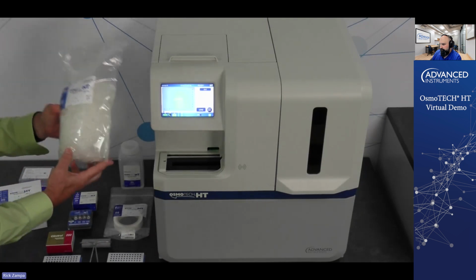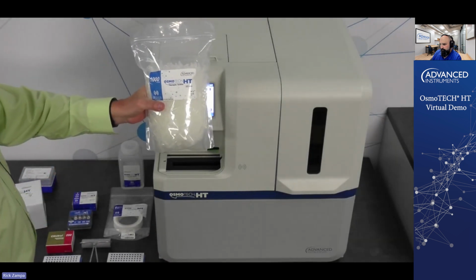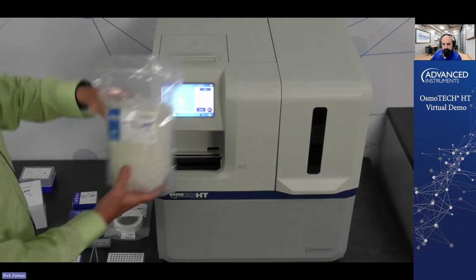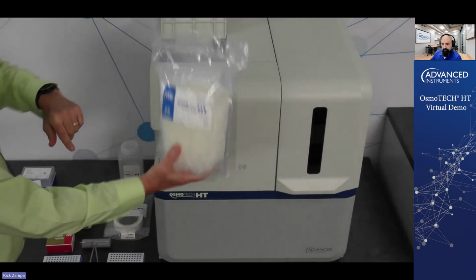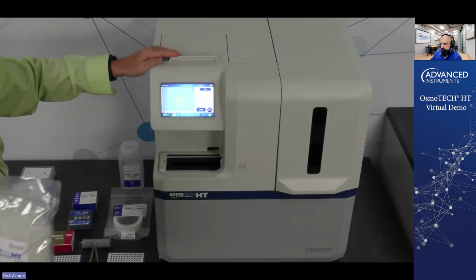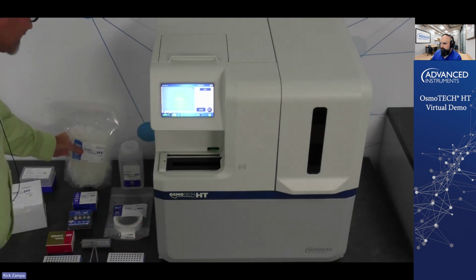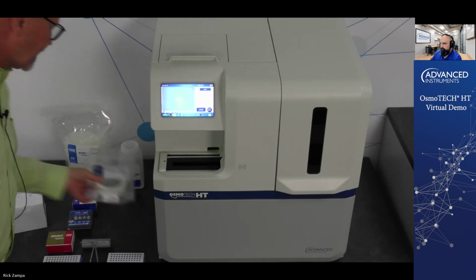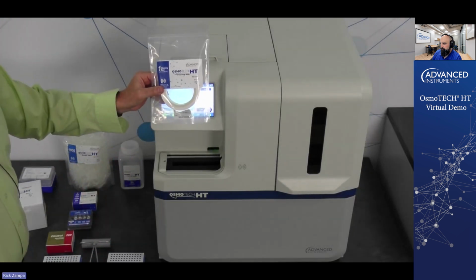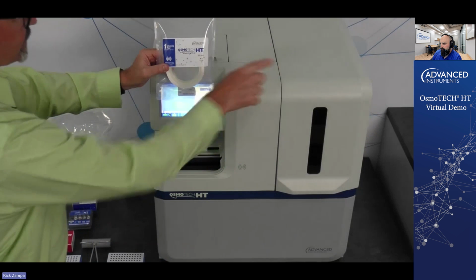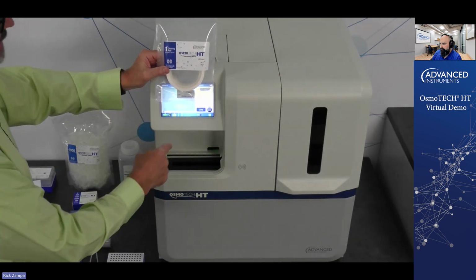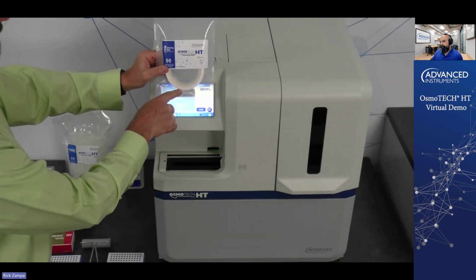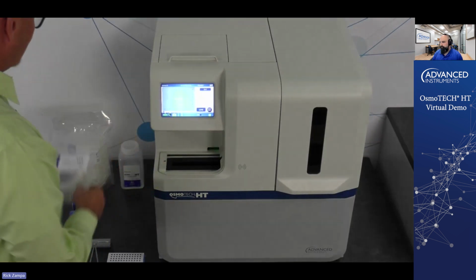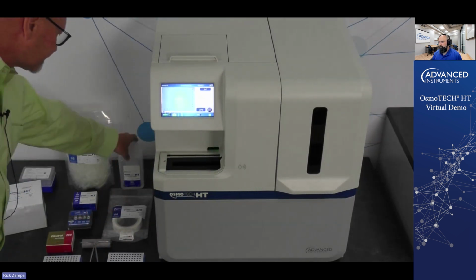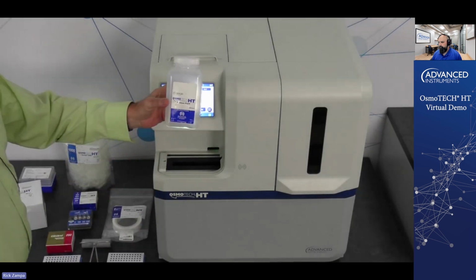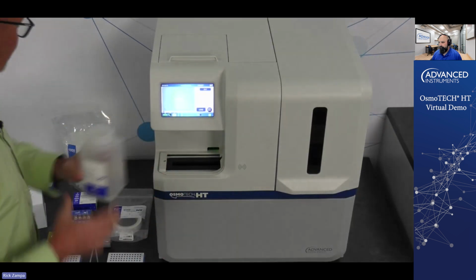The other thing that you have is your sample cups here. There are 1,000 sample cups in this bag. Those get loaded in the top of the instrument. You just open the bag, dump it in, and you load 1,000 tests, and you can run the instrument for 1,000 tests before you have to do any other maintenance. We also have our cleaning reel. The cleaning reel goes in the osmometer module over here, and I'll show you where that is later when we open that up and get a good shot in there. That cleans the sample probe between each test, allowing you to be assured that there's no carryover between your tests. You have your system cleaning fluid here, which is in the drawer and comes with the instrument.